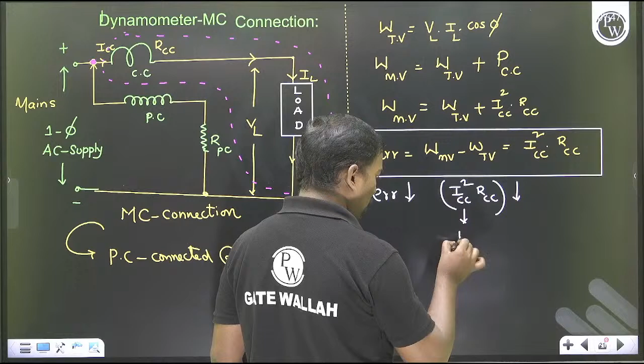So there exists an error, equal to measurement value minus true value, which is the error due to the current coil's power loss. For the error to be small, ICC square RCC must be small. Since RCC is a constructional feature and cannot be reduced, ICC must be small, meaning the load current must be small.